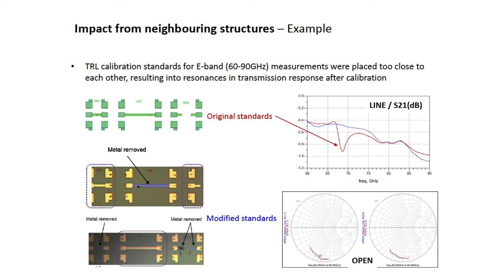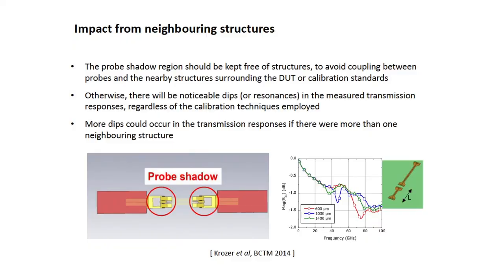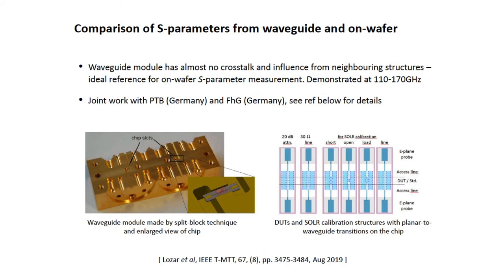After re-doing the calibration using these modified standards, the blue line shows the resonance is gone. This proves the point: coupling between the probe and nearby surrounding structures must be considered when designing devices and calibration elements.